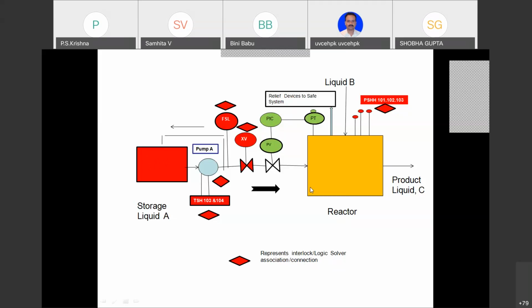So they jumped and said, we have to do something about it. The mechanical man said, we'll put a non-return valve. I've not shown you a single thing. And I will show you what we have done as instrument people: we put a low flow sensor. There are pressure and flow sensors which I have not shown you, but I am only showing you the critical one belonging to the diamond family. So this is what we have put. Okay, then we were satisfied. We got points in that, okay, we have reduced the risk so much. We all got points. Like you people get credits in the university, we got points. Because each time you do something right, you get some points or credits.